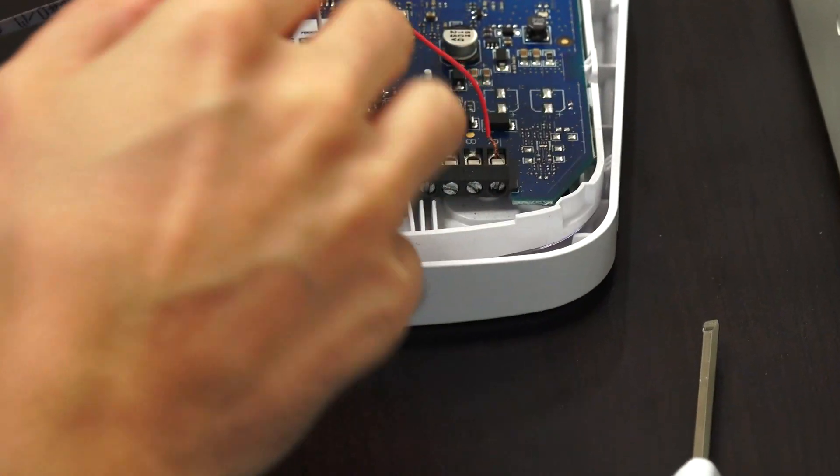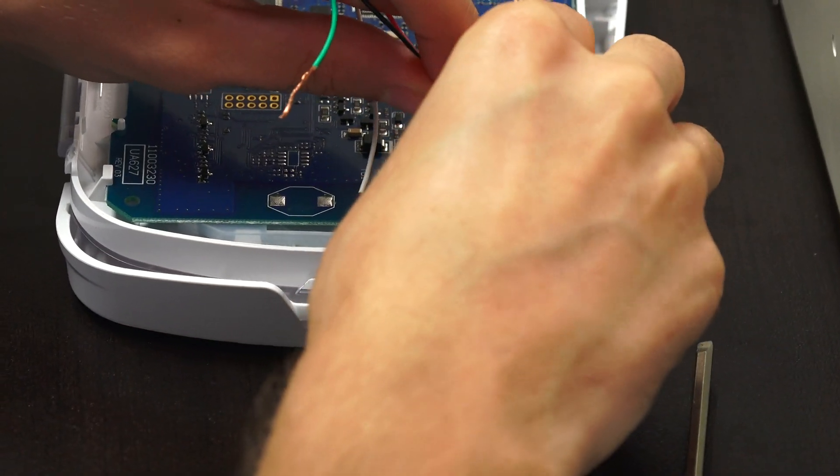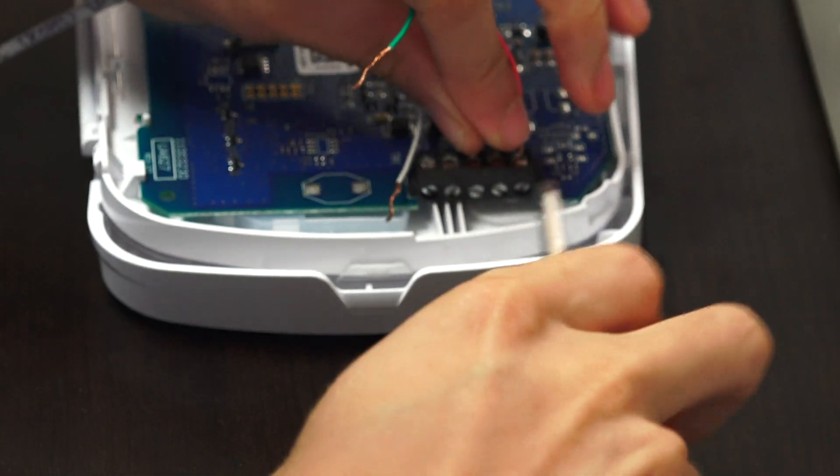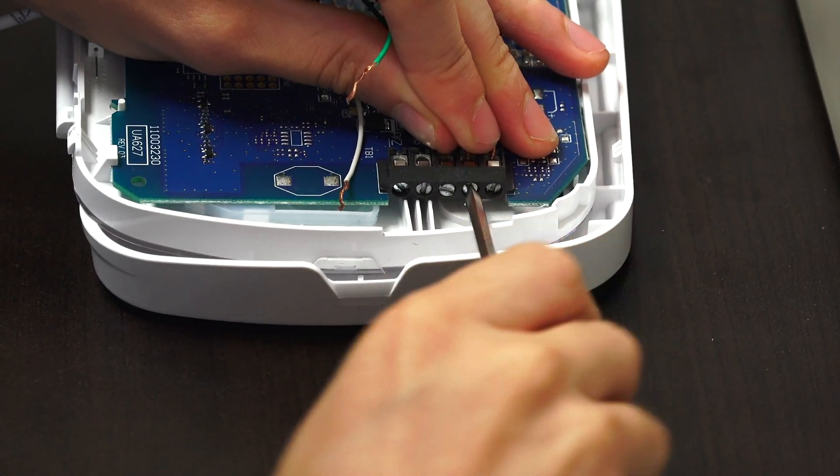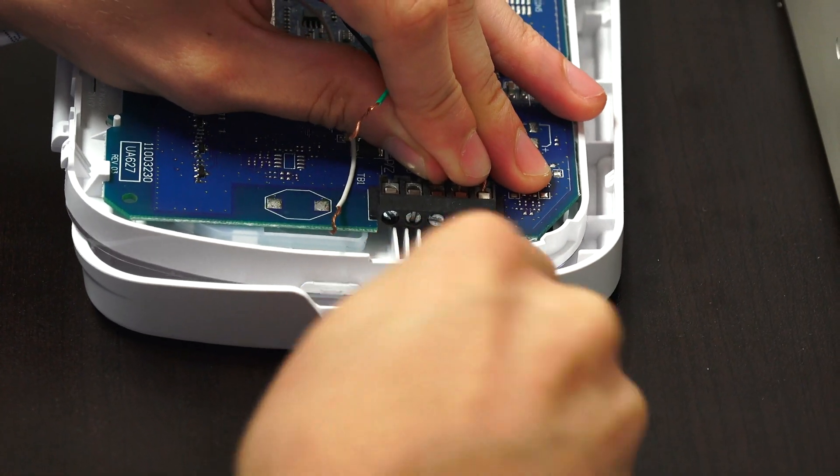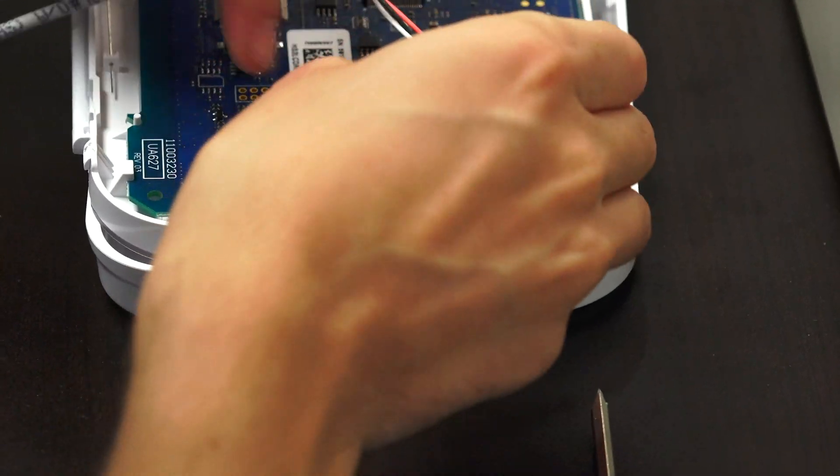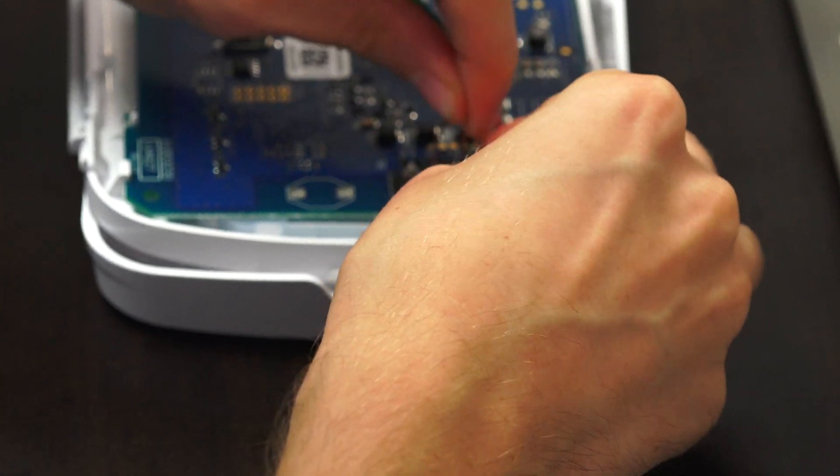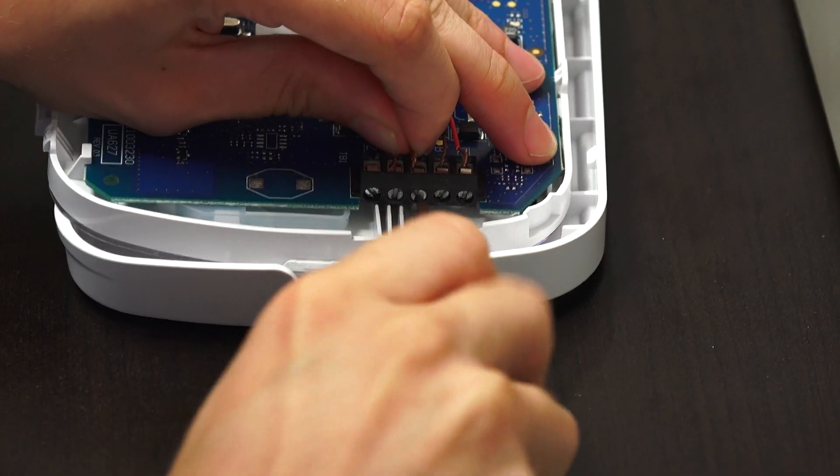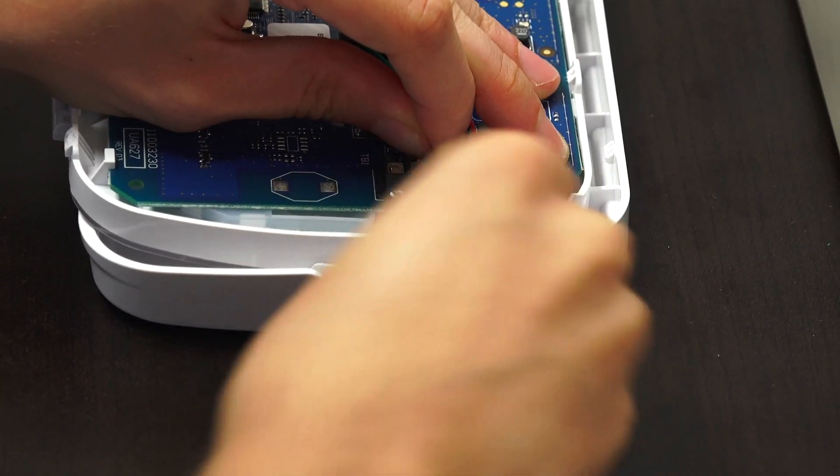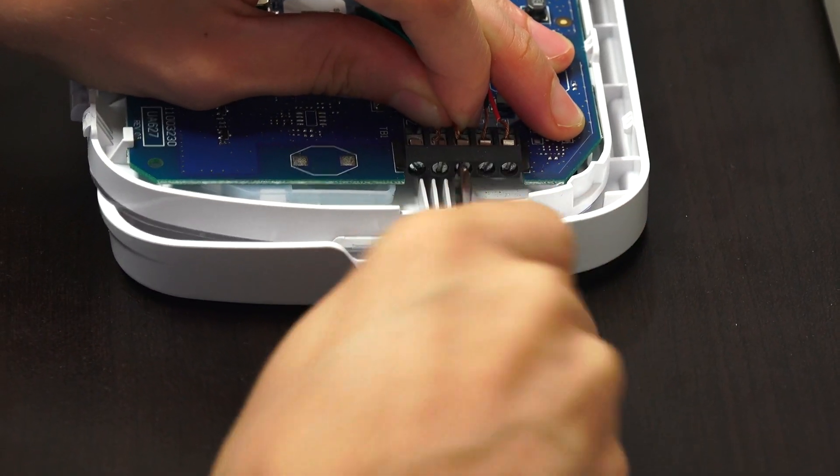Then we take the black wire into B. This is for the ground connection or the negative power. We're using stranded wire here, which is easier to strip and prepare. Next, we have Y for yellow, but in our case we have the white wire here. We'll insert the green one as well and tighten them down separately.